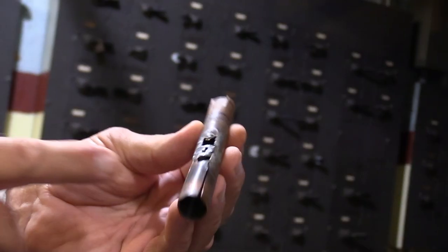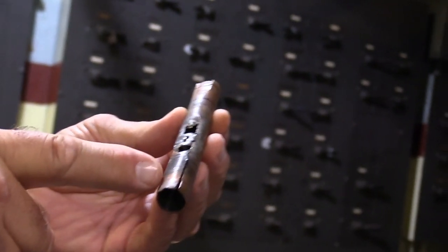You can see the holes in the bottom — these are not drilled holes. That's the bottom of the condensate return pipe. We have probably two to three thousand feet of return line for the steam, and as it comes through, it erodes the bottom of the pipe. This one got repaired, so currently we don't have any leaks, but this happens from time to time.